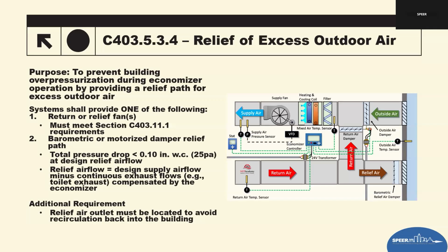Plan reviewer tips. So check whether the design uses the fan relief or damper relief. Verify pressure drop calculations for fan relief or damper relief. So it's that 0.10 inches of water column. Confirm relief airflow calculations. So supply minus continuous exhaust. Then ensure the mechanical plans show the relief outlet location and make sure it's not close to that inlet.